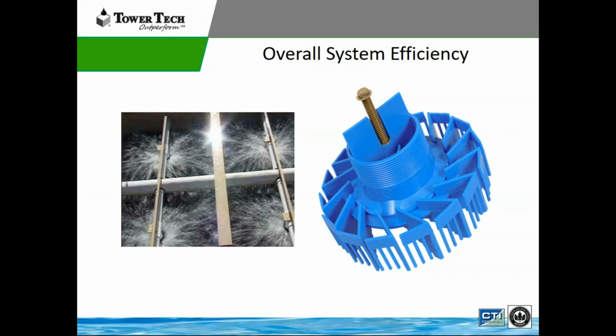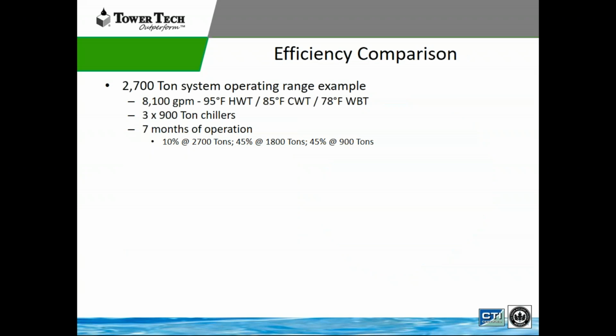Okay, this is a snapshot of the tower with the top fill off. This is just showing a site view of how the nozzle works and operates. So this is an actual design. This is an actual job in Chicago that was installed, probably 5-6 years ago. We'll show the analysis on it. This is a 2,700 ton system, 8,100 GPM, 95 entering water, 85 leaving water of the tower, 78 wet bulb. We have 3 900 ton chillers, and the operation is 7 months a year. And we're assuming 10% operation at 2,700 tons, 45% at 1,800 tons, and 45% at 900 tons.